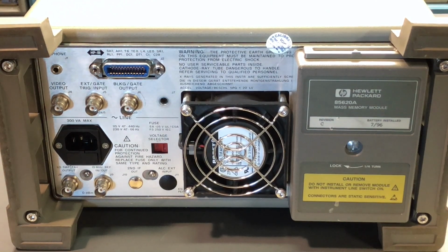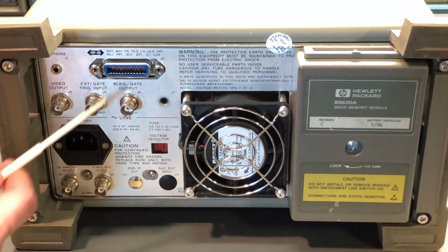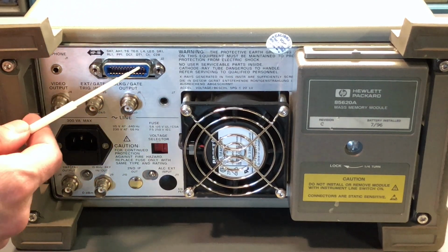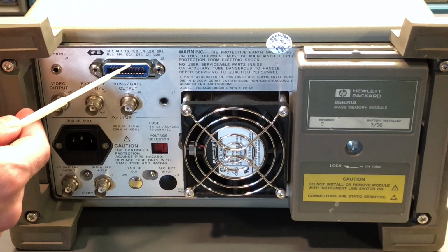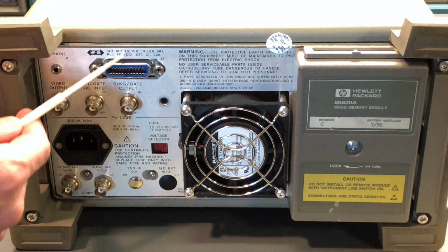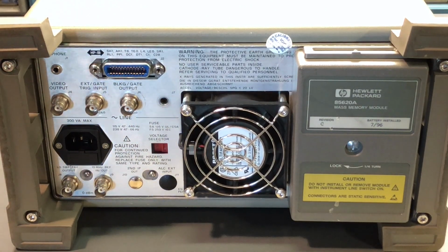Now, I do want to open up the instrument. We'll take a look around. We'll get to that a little bit later. But it's always nice to see those calibration stickers still in place. So starting over here, we can see there's a Hewlett-Packard interface bus, or HPIB. This is for remote control of the instrument. Very common. HP had those on many, many different instruments, and that's their interpretation of the GPIB bus, or general purpose interface bus.